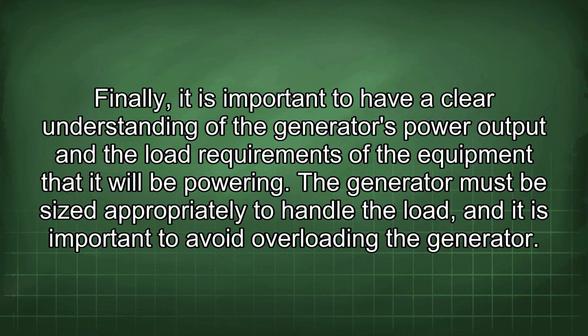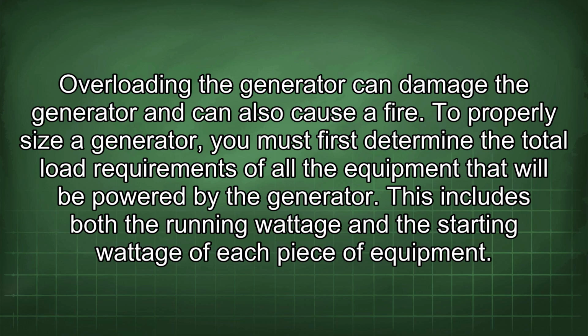Finally, it is important to have a clear understanding of the generator's power output and the load requirements of the equipment that it will be powering. The generator must be sized appropriately to handle the load, and it is important to avoid overloading the generator. Overloading the generator can damage the generator and can also cause a fire.